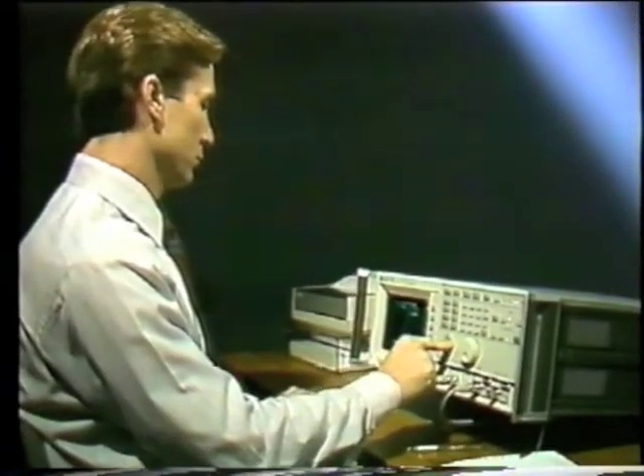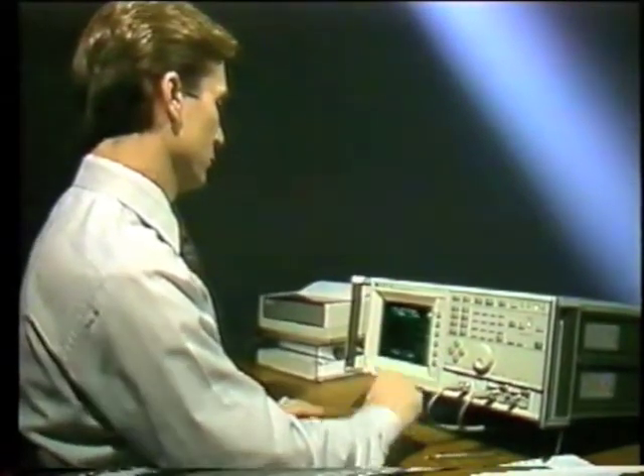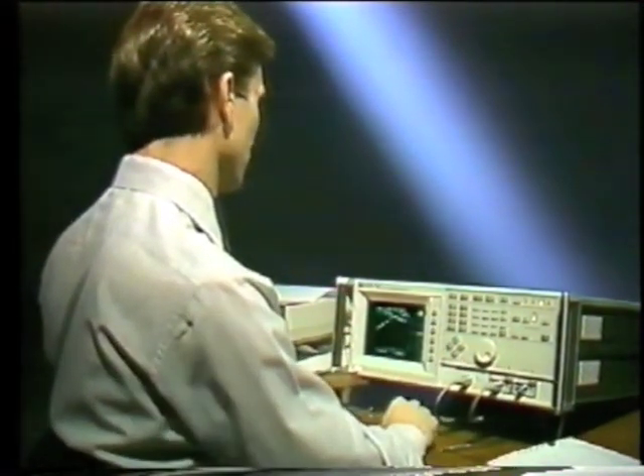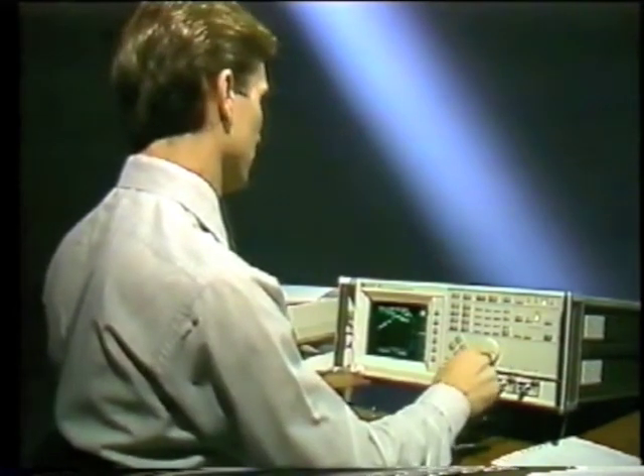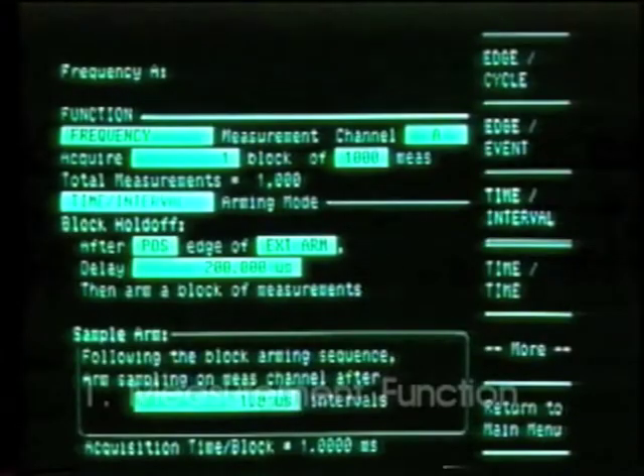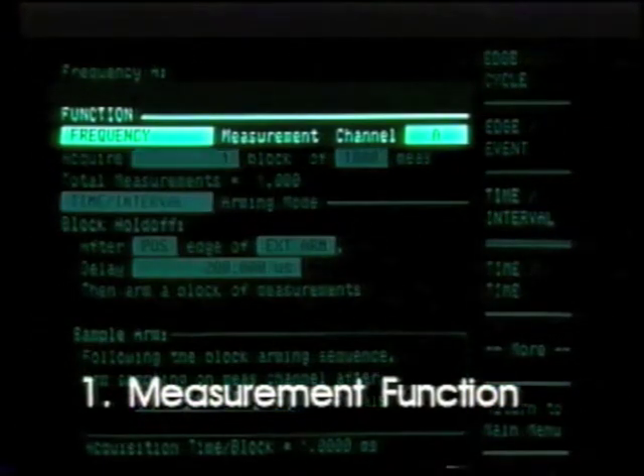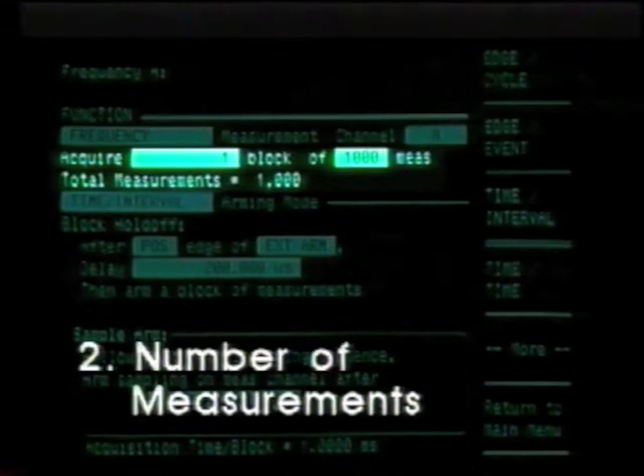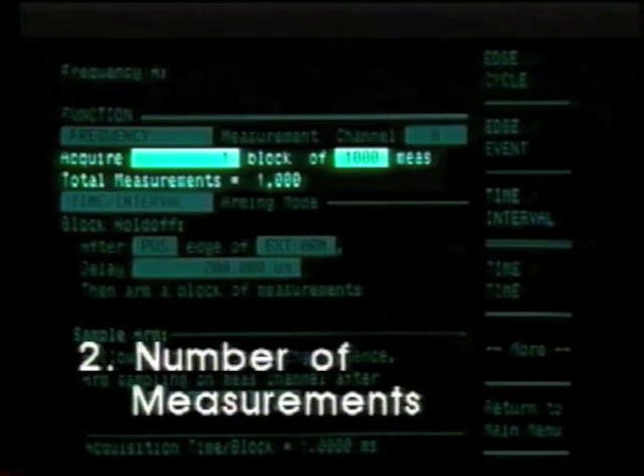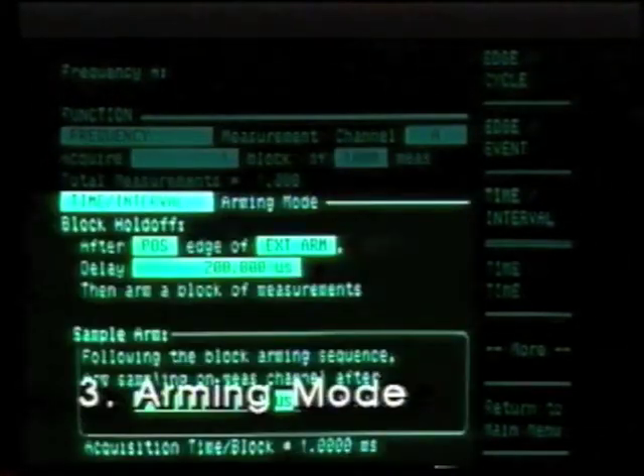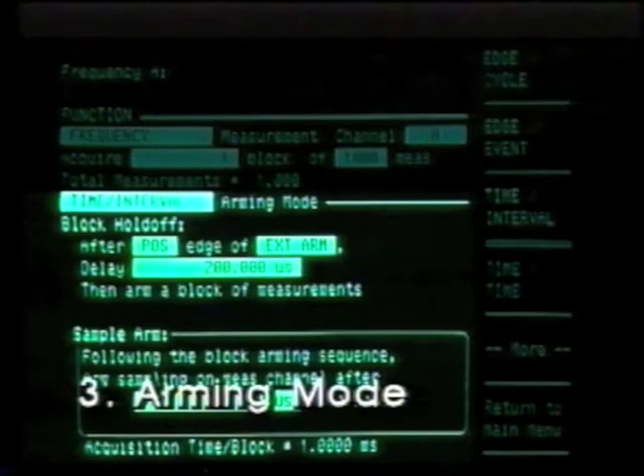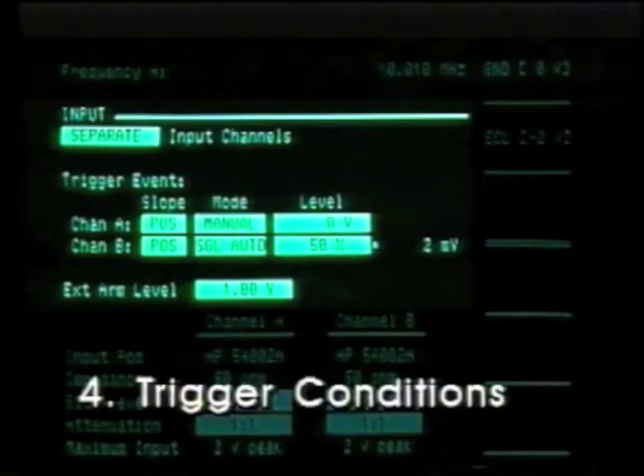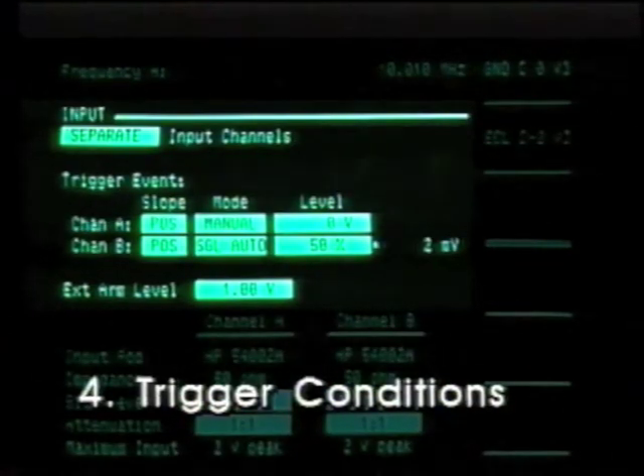Now that we've seen how the 5371A works, we'll show you how to use it. There are four easy steps to follow: first, choose the measurement function; second, select the number of measurements to be made; third, select an arming mode; and fourth, identify the trigger condition.